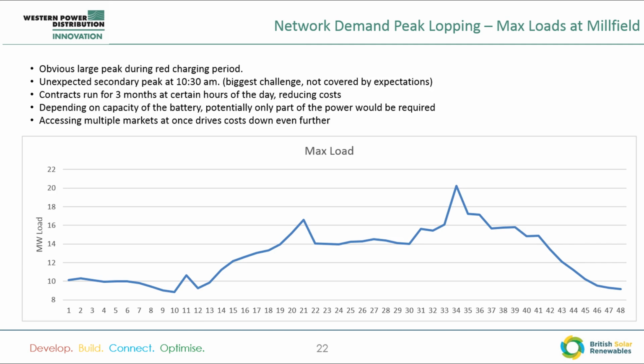Looking at trying to peak lop, we took 2 years, 2016 to 2018, and found the maximum half-hour load at any point over that 2-year period. So this is showing the maximum load that there has been in 2 years on those primaries. And what we find is that there is an absolute peak at 5 p.m. within the red period, so the actual peak does follow the national expectation.